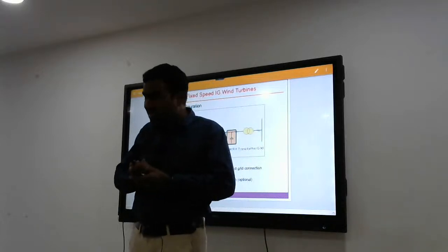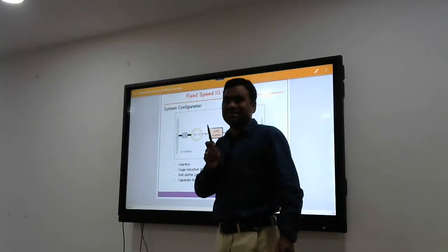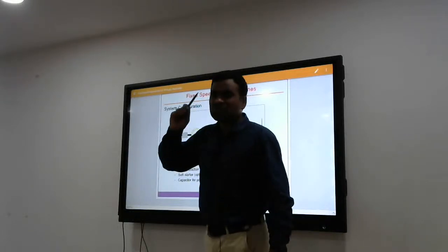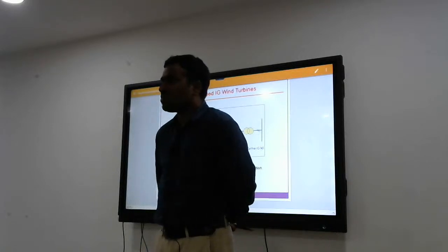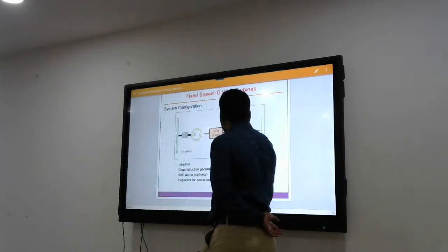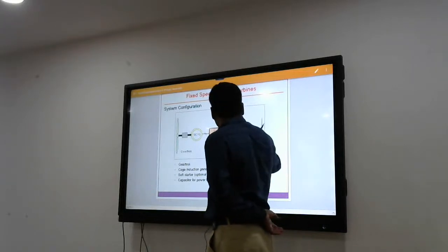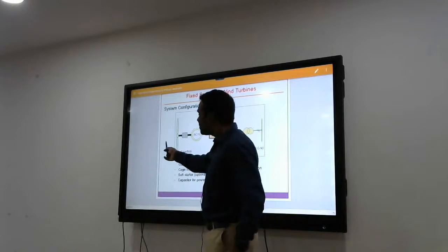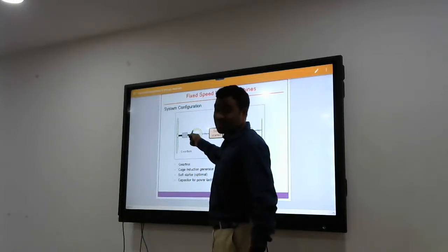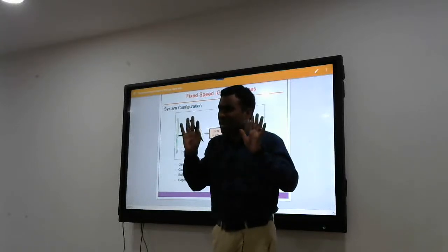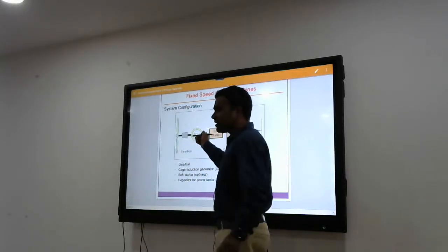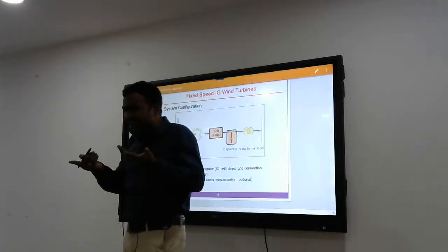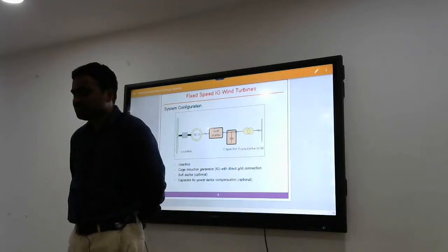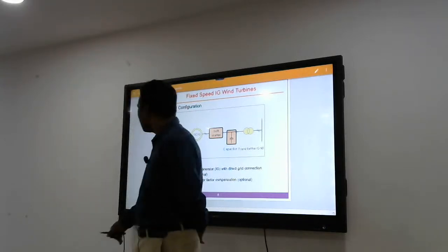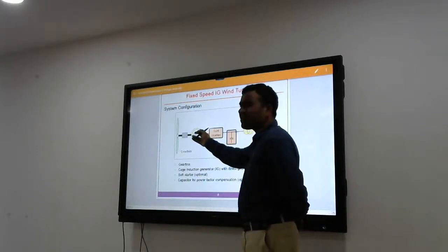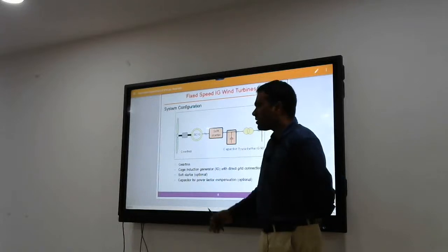But one more thing: the power is generated, but this is an induction machine, so it needs reactive power. Otherwise it can't produce any voltage. Suppose I don't connect this capacitor, it will start drawing the reactive power from the grid. Even if I make my speed greater than synchronous speed and it enters generation mode as an induction generator, it is generating active power, but it will start drawing reactive power from the grid. The problem there is, as I have mentioned, these are very huge machines, and if you start drawing that huge reactive power from the grid, it may collapse. Voltage instability problems may occur.